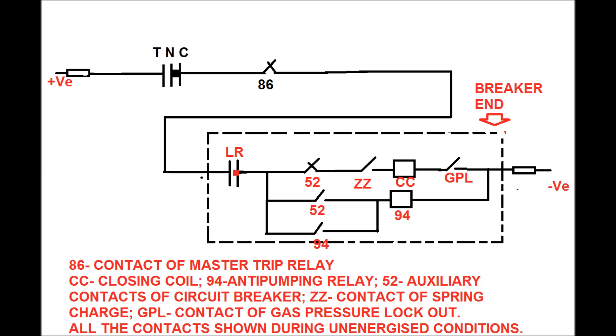94 is the anti-pumping relay and its auxiliary contact is shown in this figure. GPL is the gas pressure lockout contact. If gas pressure is normal then this contact is in close position.